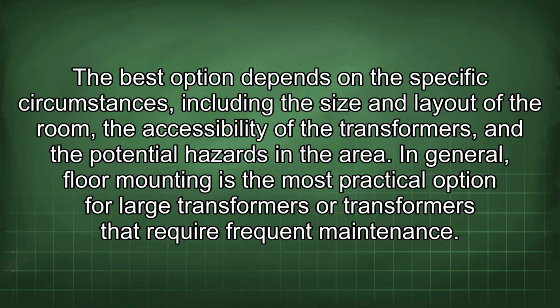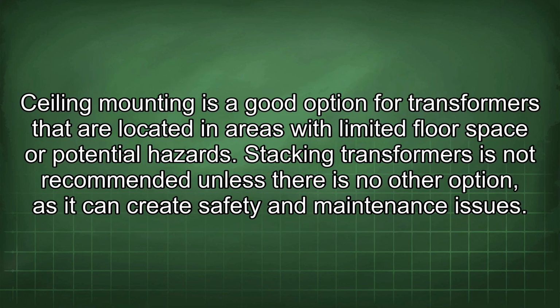The best option depends on the specific circumstances, including the size and layout of the room, the accessibility of the transformers, and the potential hazards in the area. In general, floor mounting is the most practical option for large transformers or transformers that require frequent maintenance. Ceiling mounting is a good option for transformers that are located in areas with limited floor space or potential hazards. Stacking transformers is not recommended unless there is no other option, as it can create safety and maintenance issues.